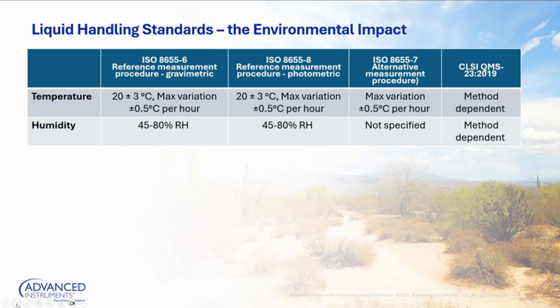Now, if you take a look at the ISO 8655 Part 7 column, that's the alternative measurement procedure. Gravimetry and photometry are also mentioned in Part 7, but it's a little bit less stringent of a process. Specifically, ISO doesn't indicate in Part 7 the specific temperature your lab needs to adhere to, although they do mention that it shouldn't be shifting more than 0.5 degrees Celsius per hour. But they don't specifically recommend humidity levels for your lab. And then when we get over to the clinical standards, CLSI QMS 23, they just indicate that it's method dependent. So a lot of ambiguity, but also a lot of autonomy. If you take that glass-half-full mentality, that means that you've got the ability to define it yourself.